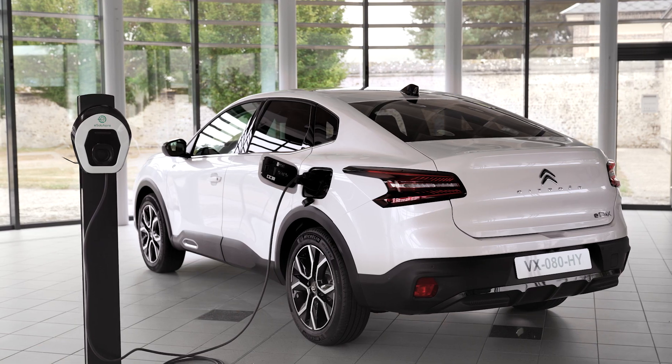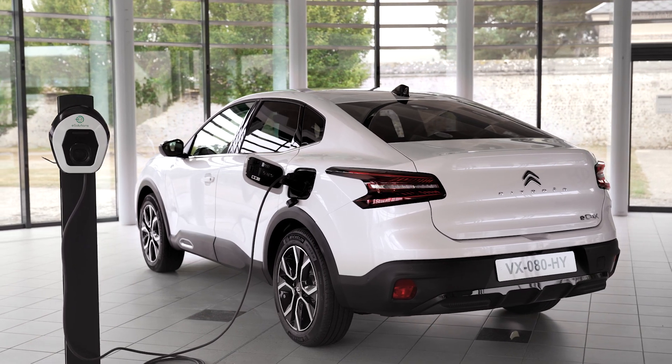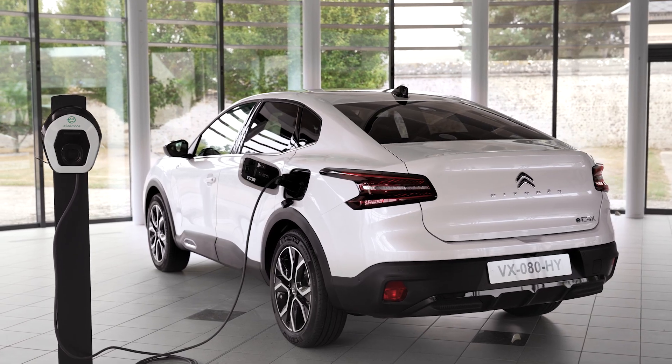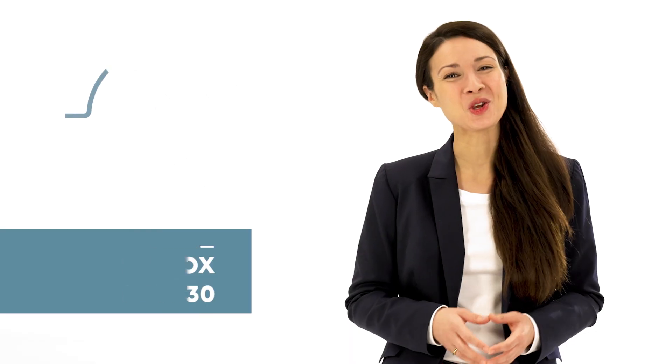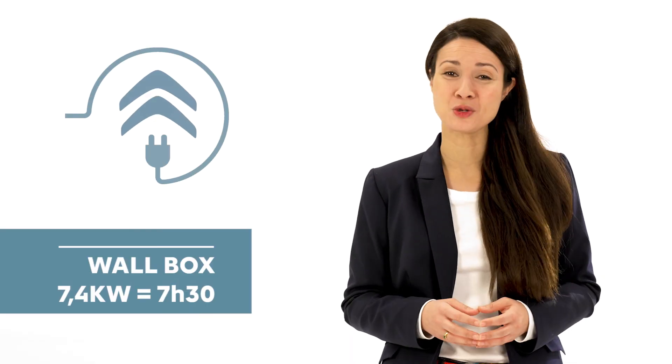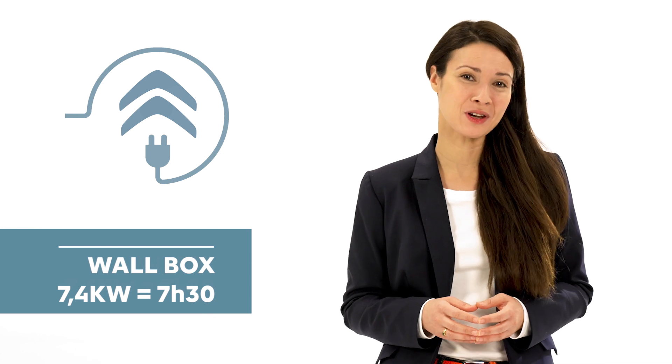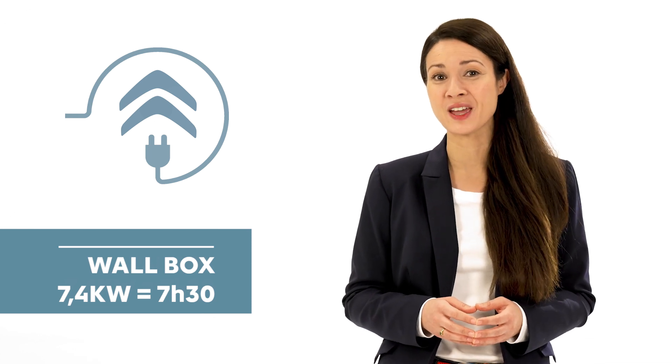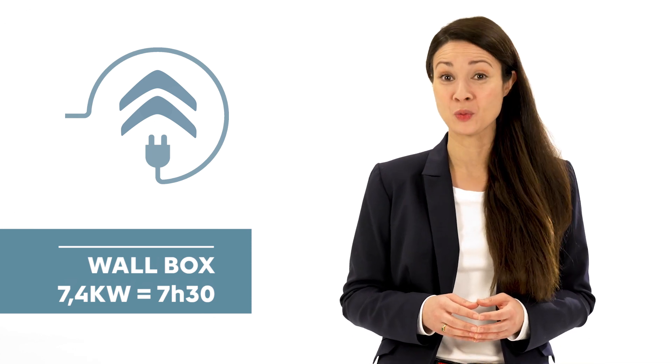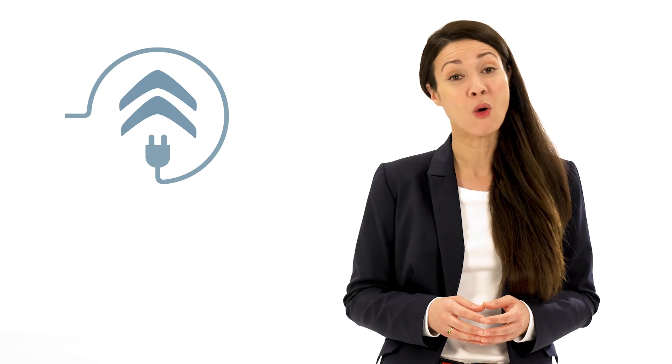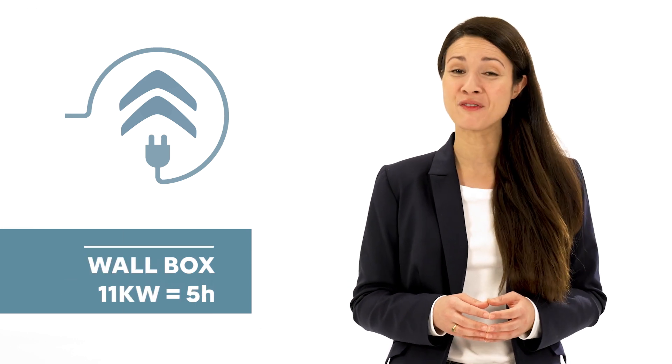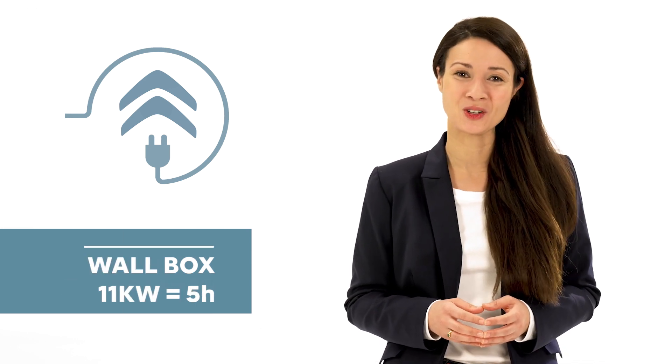Finally, rapid domestic charge with a Mode 3 cable requiring the installation of a 3.7 to 22kW rapid charge wallbox. Charge time from 0 to 100% will then be 7 hours and 30 minutes for a single-phase 7.4kW wallbox or 5 hours for a 3-phase 11kW wallbox. This wallbox can be installed at home by an approved installer.